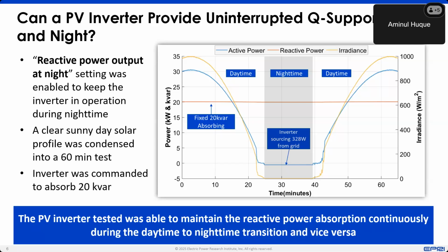And then we basically try to mimic a middle of a day, noon to next day noon period, with irradiance going from top or maximum to zero, staying in the nighttime and then waking up. So this orange curve mimics the irradiance profile of a whole day, but we squeeze that into a 1 hour period for running testing in the lab. So we used a PV simulator where we uploaded this irradiance profile and the output DC power was fed to the inverter to see how the inverter operates.